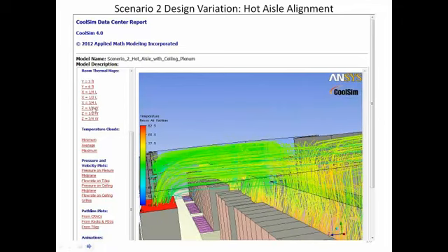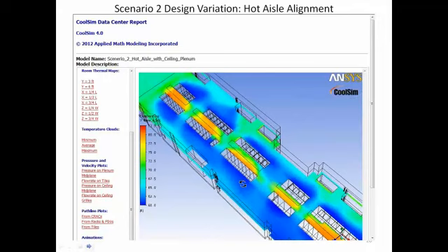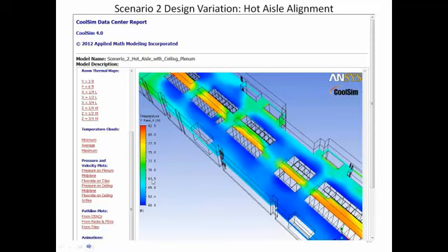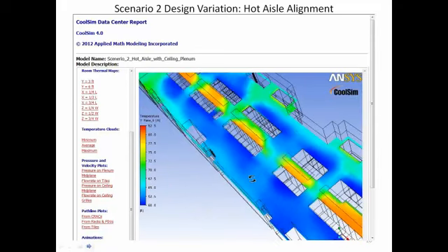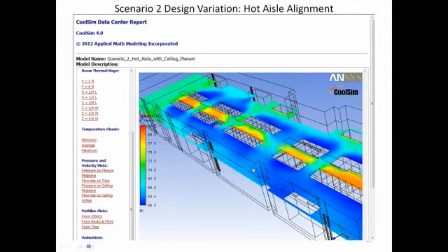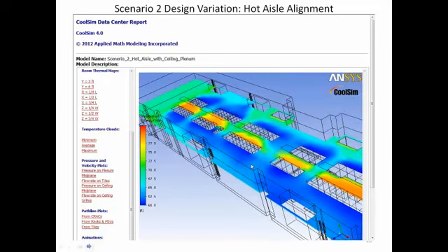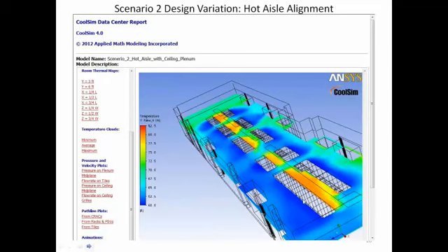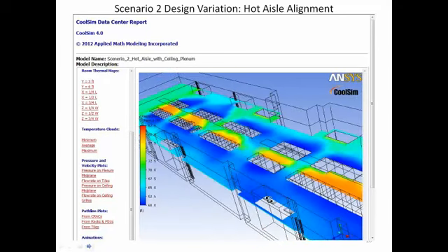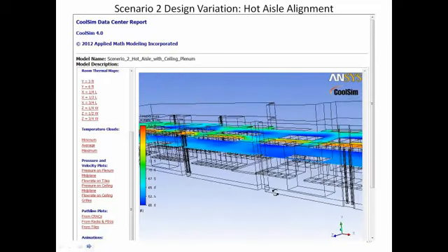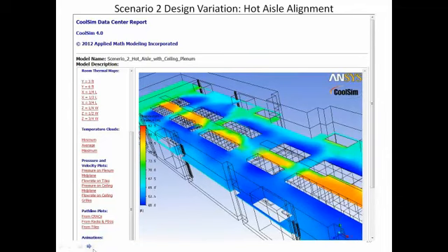Yep. Now, the good news about this kind of configuration, if we go back to that same plot we were looking at before with respect to temperature, is the room's cool. I mean, I prefer hot aisle whenever I can get it, and this is why. It has less to do with thermodynamics, Matt, and more to do with the human factor. Correct. Here we've got the room running in the 60s for the most part. The hot aisle is running up to 80. But at least when someone enters that room, they don't run for the thermostat and try to turn it down. Exactly. And this is what I find in cold aisle containment configurations: someone's always trying to turn the temperature down because they feel it's too hot, when in fact they don't realize that they're standing in the hot aisle when you do either cold aisle containment or cold aisle alignment. So that's two. That one looks like the better one at this point.